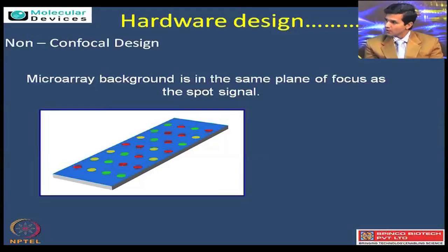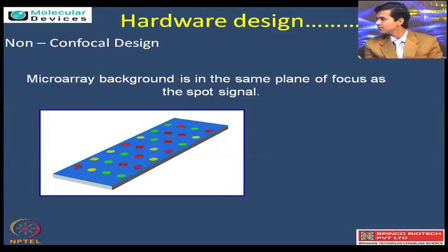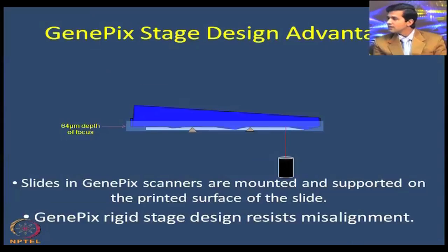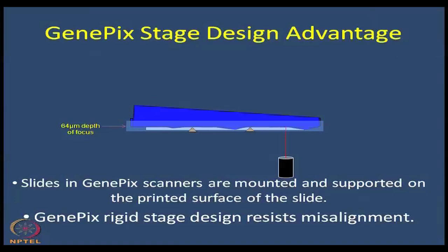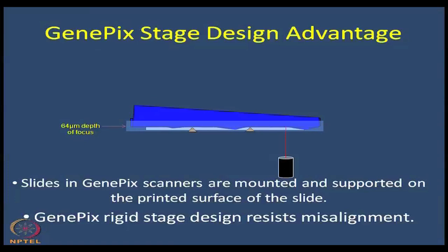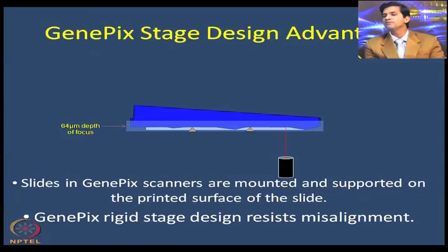That is why non-confocal design is chosen, coupled with the inverted design of scanning, which helps achieve the best results in the form of signal-to-noise ratio. Usually in glass slides there are a lot of small deformities which our eyes cannot see. What we do is invert the slide so that it goes to the level of the same scanning plane and is supported at the edges with controllers which account for the deformities in the glass.